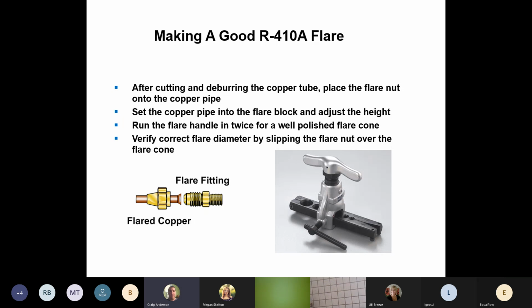Good flaring tools, like we talked about before. When we're doing our flare, make sure we've got good cutters, deburring tools, and a good set of flaring tools. Let's make sure we get a good flare. If you're going back to get a bigger wrench, then that's not the problem. There's something going on with your flare or your flare nut. So make sure that you have a good flare and you're ready to go.